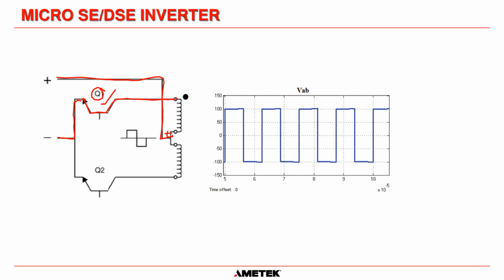Okay. And I'm not going to go into transformer design too much, but whenever you see a black dot, that means that's where the winding starts. And then obviously this is where the winding ends. So we're making a positive signal compared to the negative signal on this transformer. So in truth, what that is going to do is it's going to give us this bottom half, because look, here's 0 and then we turn Q1 on at this point here, and we go straight up. This graph here shows it as 100 volts. So let's say we've got 100 volts DC coming in. So if you measure on this side, let's say the secondary of the transformer was here, this is what the output is. If we had an oscilloscope and we switched Q1 on and then switched it off, it would give us this square wave here. So that gives us 1/2 of the square wave.